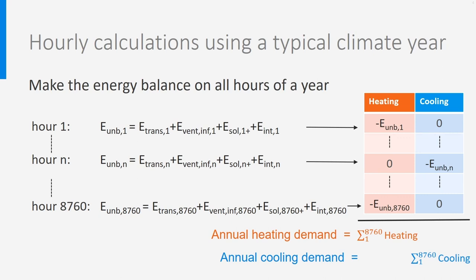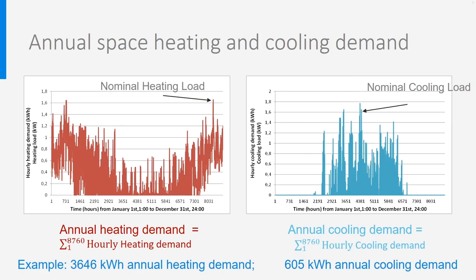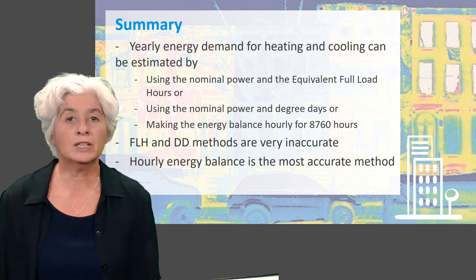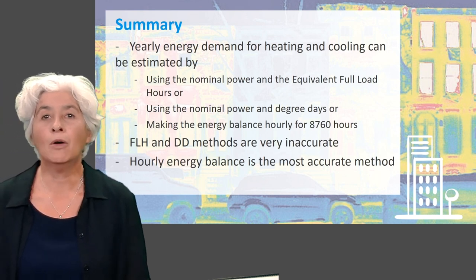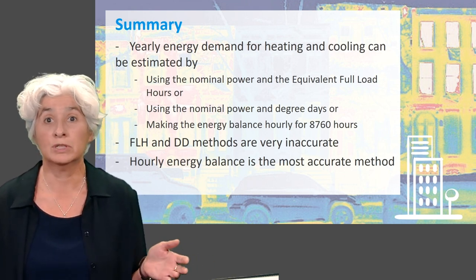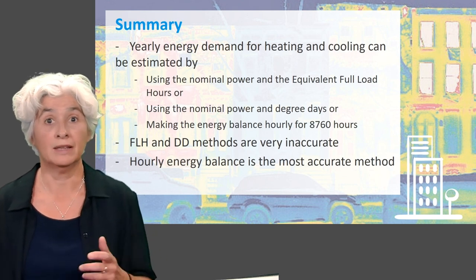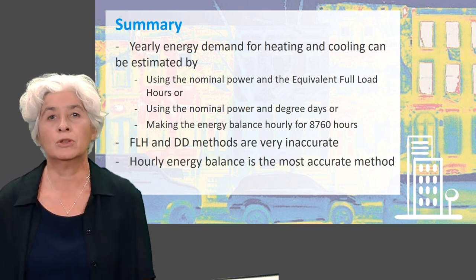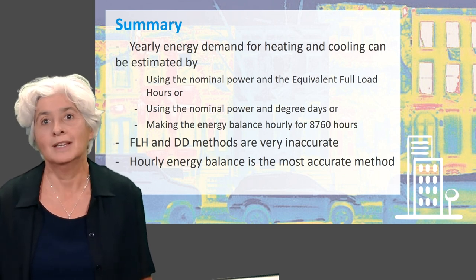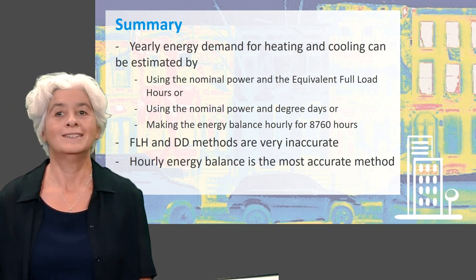Quite easy in the end. The calculations give 3646 kWh annual heating demand and 605 kWh yearly cooling demand, and I also plotted the graphics with all hourly loads. To summarize this lecture, we have seen three different methods to estimate the annual energy demand for heating and cooling: the full load hours, the degree day method, and finally making hourly energy balances for each of the 8760 hours of a year using meteorological data. The full load hours and degree day methods are easy to use as they need very few climate data, only the extreme temperatures and maximum solar radiation, but they are also very inaccurate. That is why making hourly energy balances is the preferred method. Thank you for your attention.